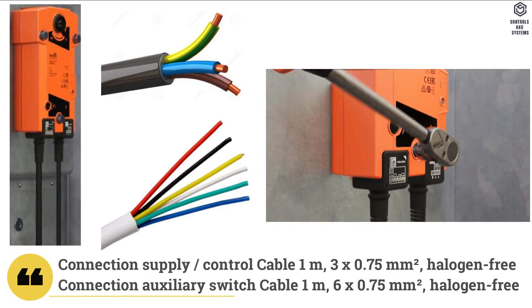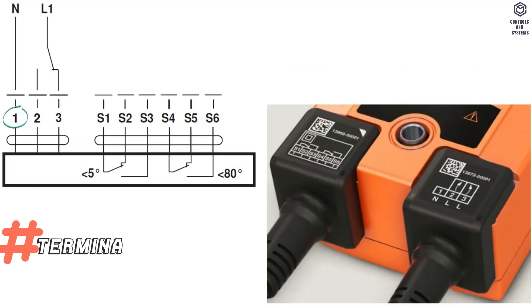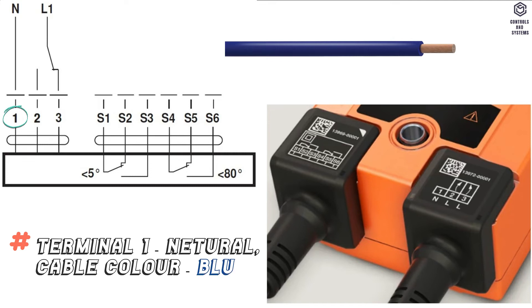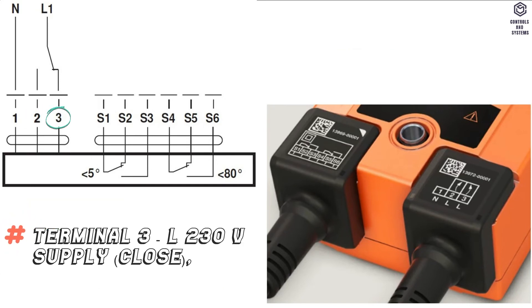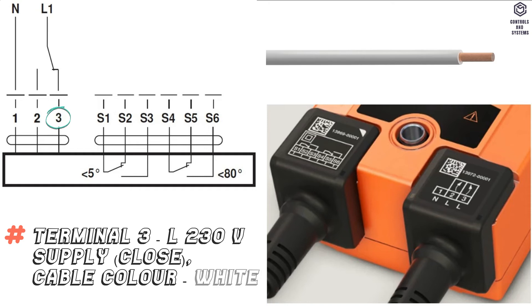Terminal 1 is neutral, cable color is blue. Terminal 2 is 230 volt supply for open, cable color is brown. Terminal 3 is 230 volt supply for close, cable color is white.